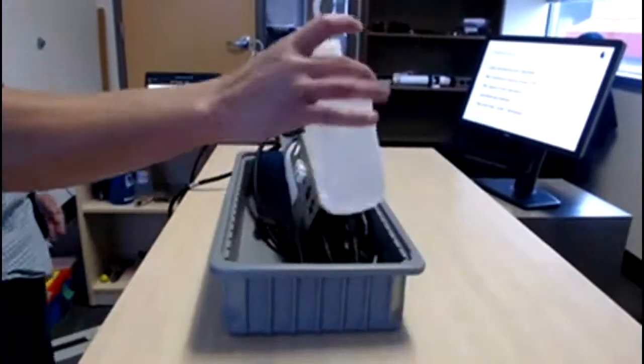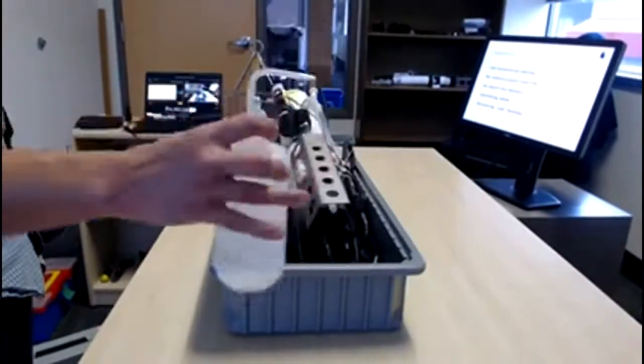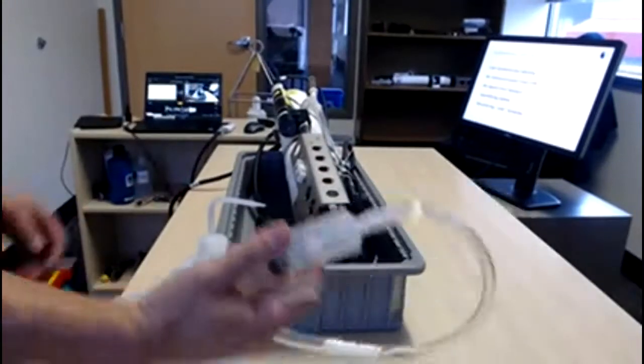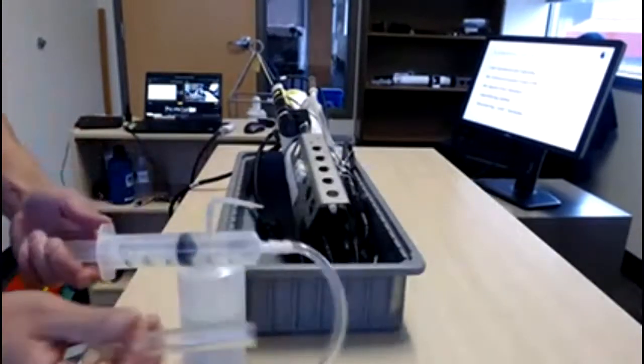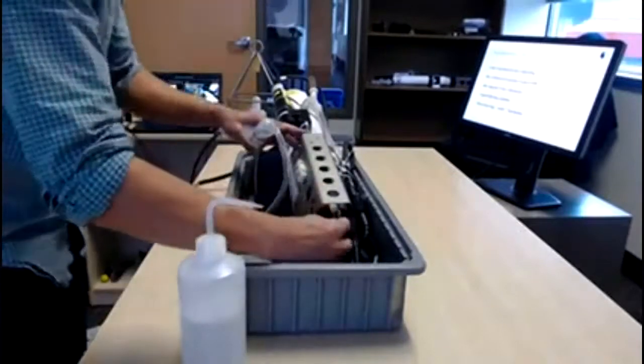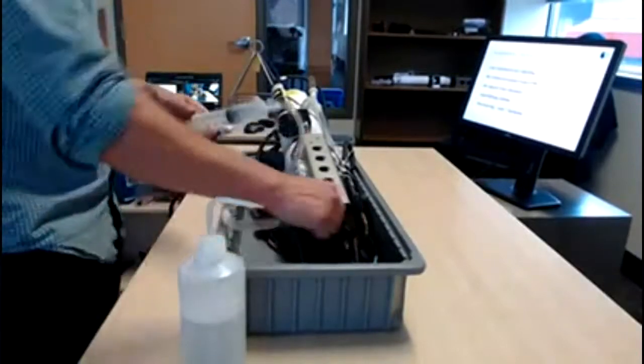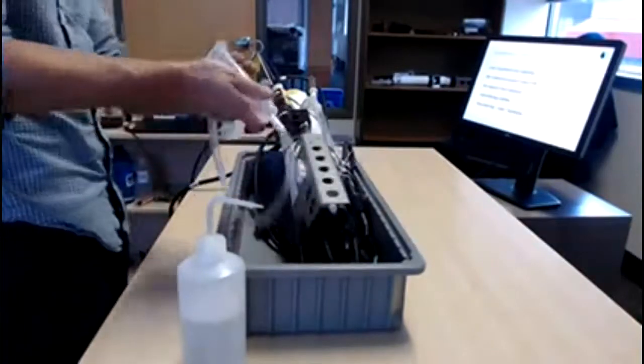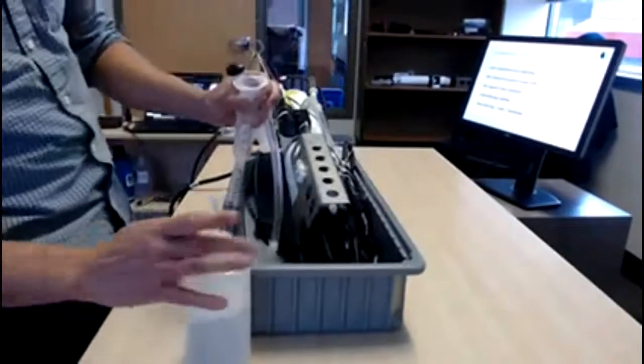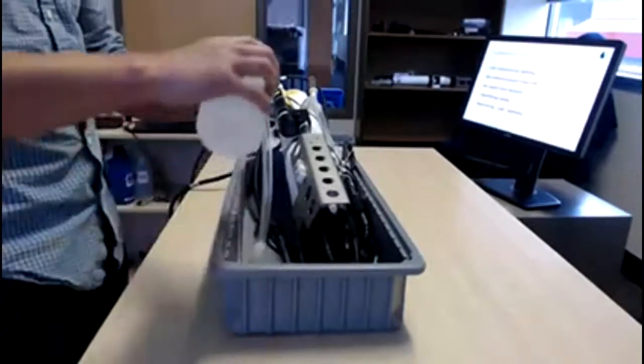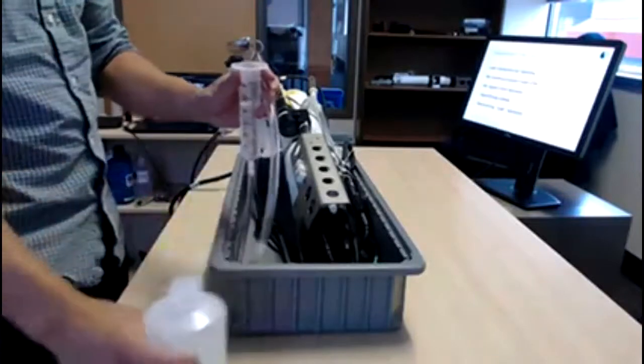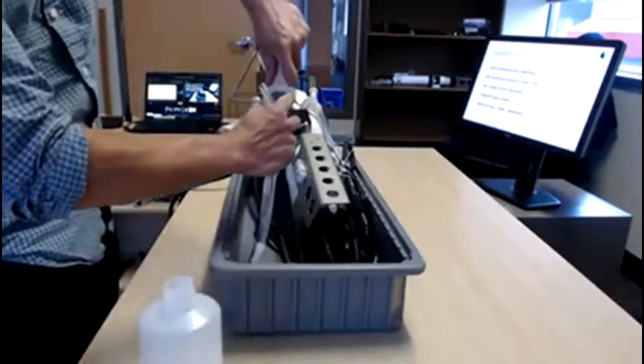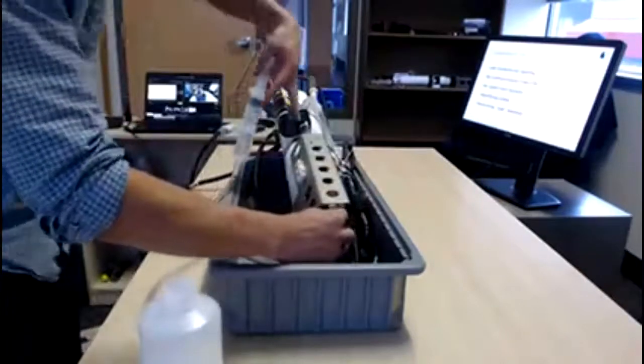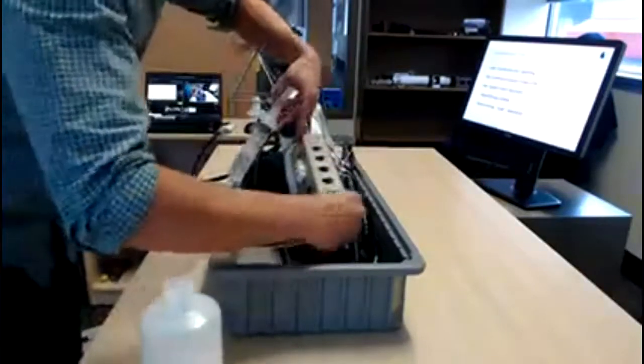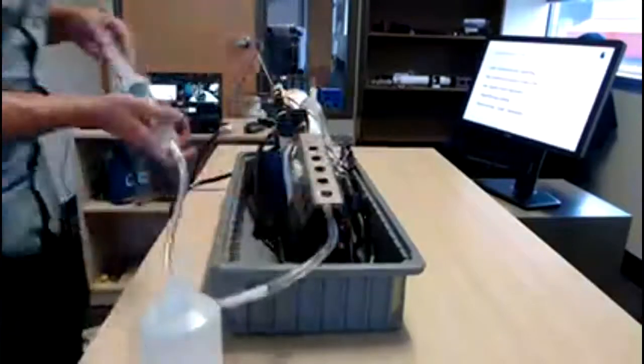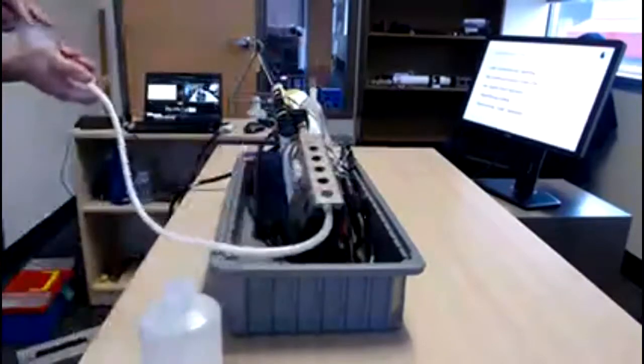This bottle is filled with a 1% solution of Triton X, and the rest is DI water. And this is part of the cleaning kit that comes with your instruments, a plastic syringe with tubing that fits onto the end of your conductivity cell here. So basically all that we're really going to do here is fill this syringe up with our dilute Triton solution, connect it to the end of the conductivity cell on this hose barb attachment, and then run it back and forth.